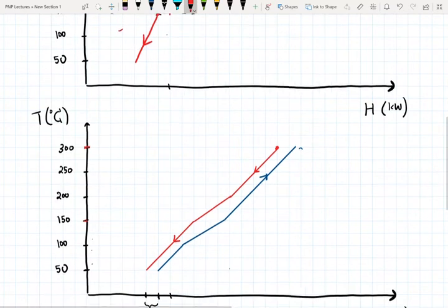Now once you have both of your composite curves, your hot curve and your cold curve, the next step is to find the location of the pinch point or the delta T minimum. You want to start off by assuming a minimum approach temperature of 0. Now depending on your minimum approach temperature, you can move this either left or right, not up or down, just left or right.